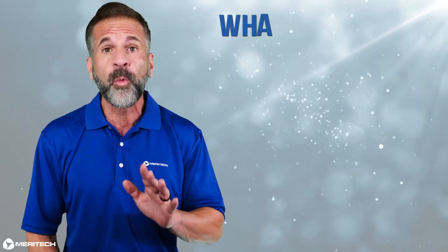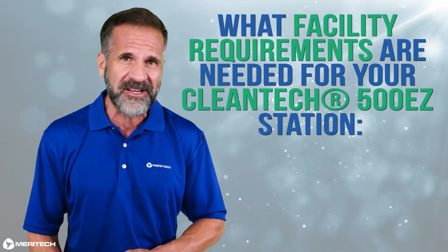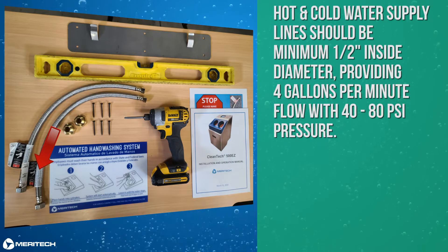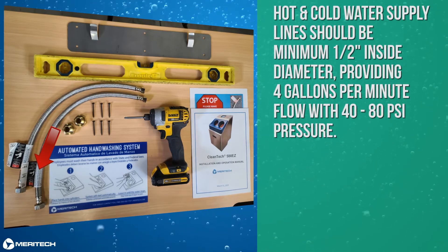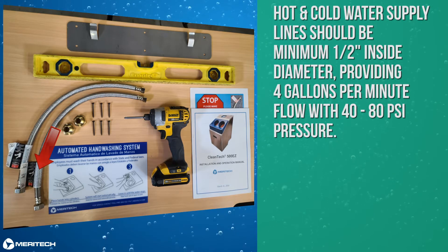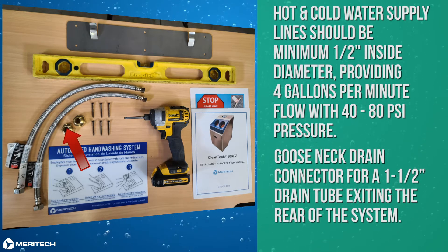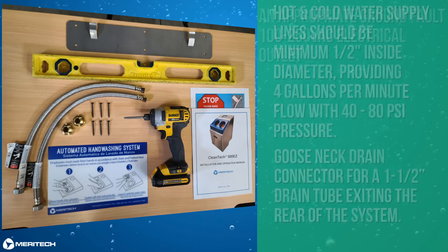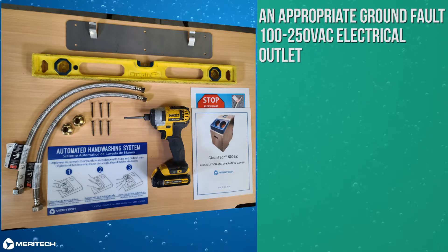Let's review what facility requirements are needed for your Cleantech 500EZ station. Hot and cold water supply lines should be minimum 1/2 inch inside diameter, providing 4 gallons per minute flow with 40 to 80 psi pressure. You will need a gooseneck drain connector for a 1.5 inch drain tube exiting the rear of the system. An appropriate ground fault 100 to 250 volt electrical outlet.